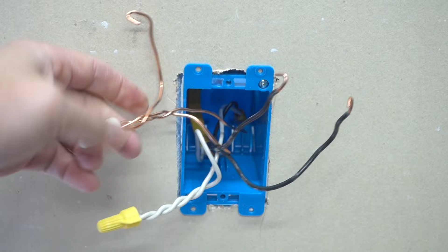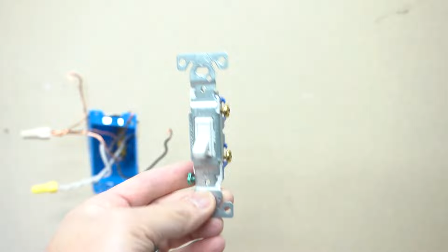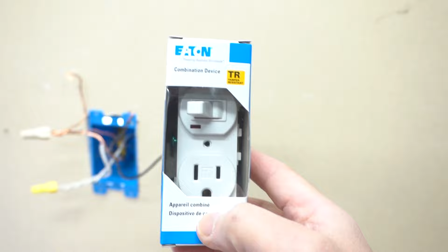In this example, what I have here is two neutrals together and three ground wires. This ground wire we're going to connect to the new device, and this one as well. We're going to be replacing the single pole switch we just took out with this outlet and switch combination, also known as a combination device.